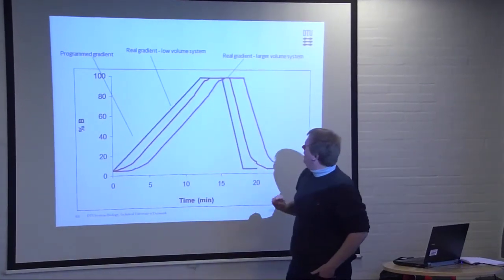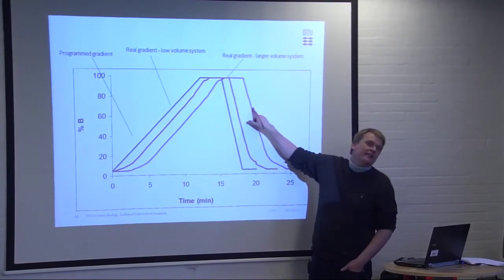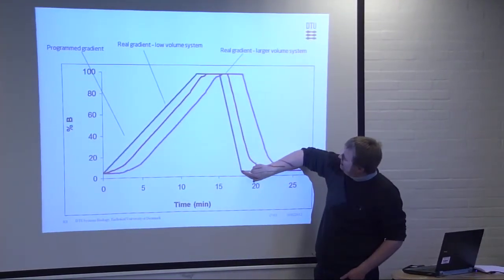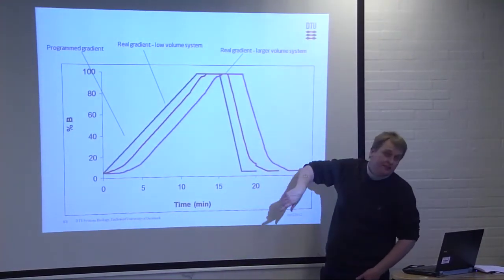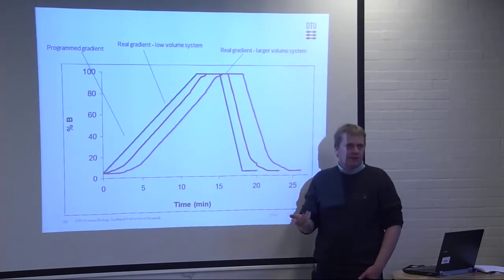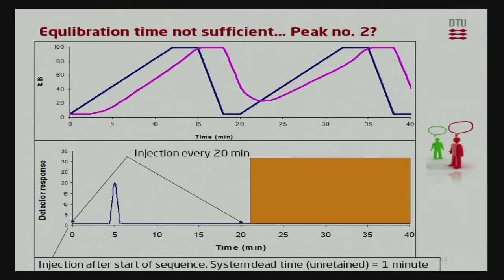So, recall this is a really, really important part, also because when you go the other way, you can program this one down, but you have a delay. So, what you type into your gradient table is not what you get.